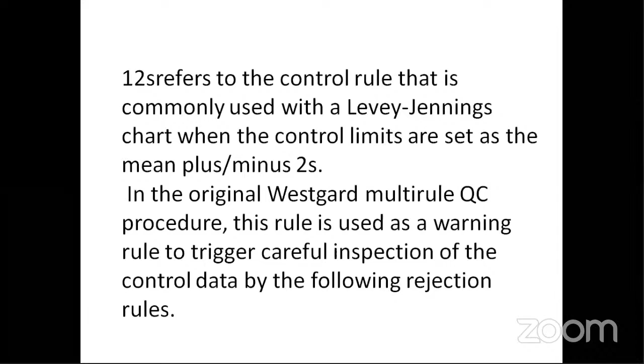If you rerun and you find a similar 2 standard deviation minus as the first, or 2 standard deviation plus as the first, it should be on the same side of the graph. If you have this, that means you have an error in the system, and this is no more a random error, this is a systematic error. You have to reject your measurements if you have a plus 2s or minus 2s control limit exceeded by 2 consecutive runs.